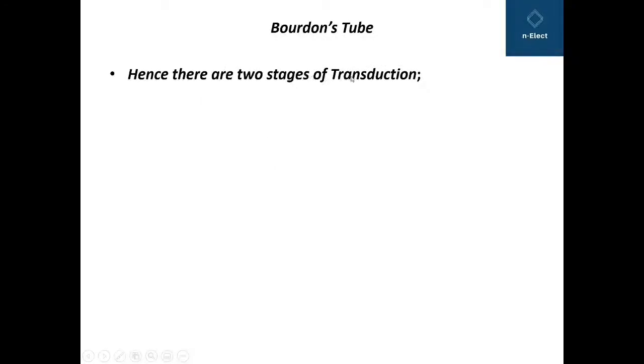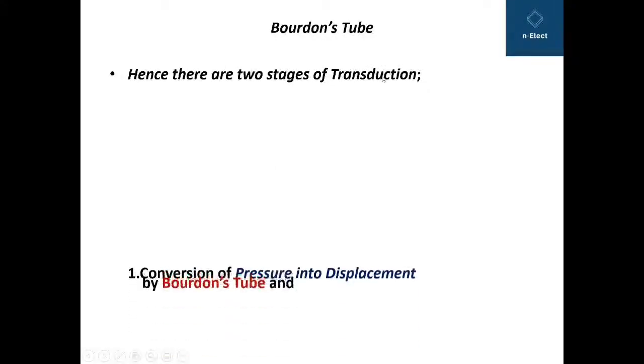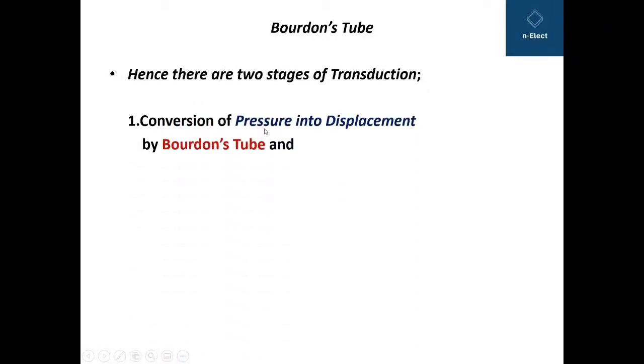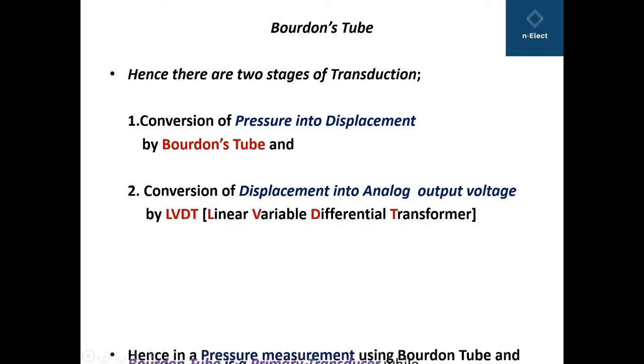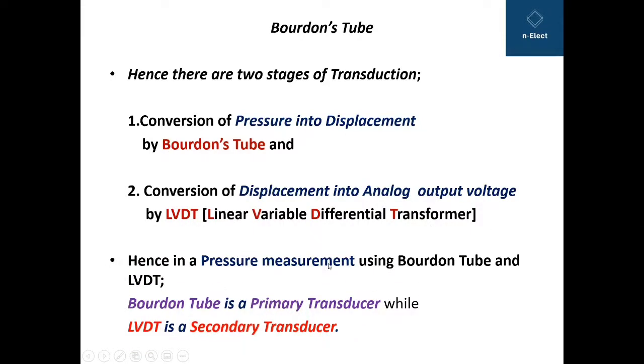Hence, there are two stages of transduction. One is conversion of pressure into displacement, which is done by the Bourdon tube, and the second is conversion of displacement into analog output voltage, which is done by the LVDT. Hence, in a pressure measurement system using a Bourdon tube and LVDT, the Bourdon tube is the primary transducer while the LVDT is the secondary transducer.